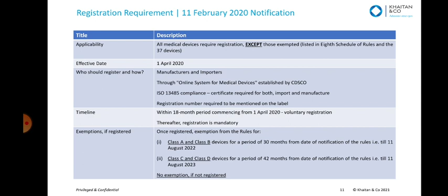As for the timeline, for the first 18 months from 1st April 2020, the registration is voluntary. After the 18 months, the registration becomes mandatory. Now, what are the exemptions? Once you register, if you're a class A or B device, you get an exemption from the applicability of the medical devices rules for 30 months, which is up to 11th August 2022. If you're a class C or D device, you get an exemption for a period of 42 months from the date of the notification or the amendment, which is 11th August 2023. If you do not register, then no exemption is available. So it's important that businesses note this and initiate the registration process for their devices.